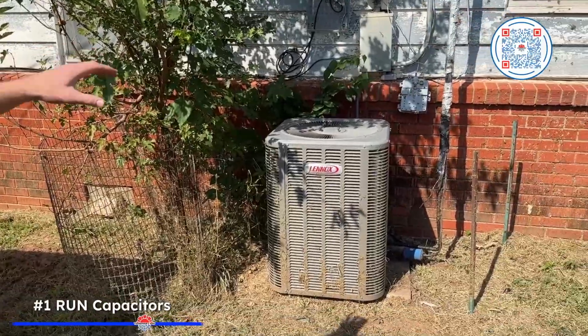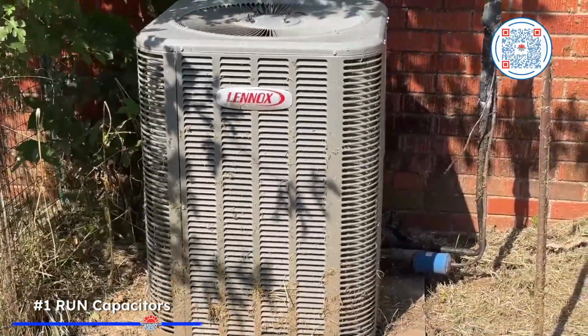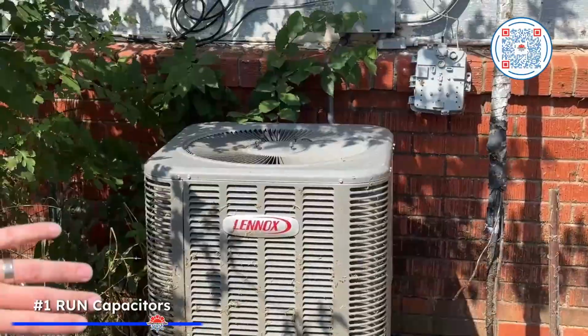And again, that's to prevent it from failing on the hottest day of the year. Run capacitors fail because of heat. There's a lot of things that go into that. Number 1 is just the ambient temperature. Whenever it's hot outside, you have a metal box that's sitting directly in the sun. It's going to get some heat in it. That's one reason. Heat from components that are not operating properly, your compressor, your fan motor, things of that nature, could cause your capacitor to overheat and then go out. That's probably the most common repair that we see, the run capacitor.